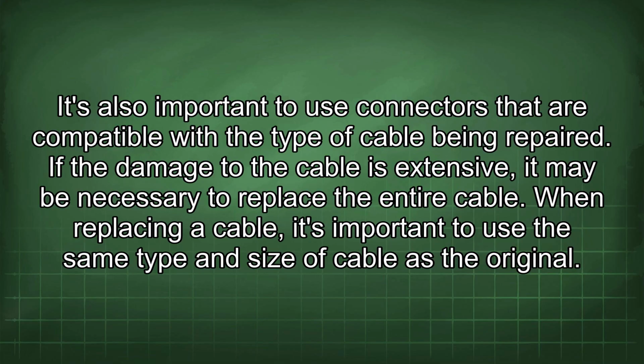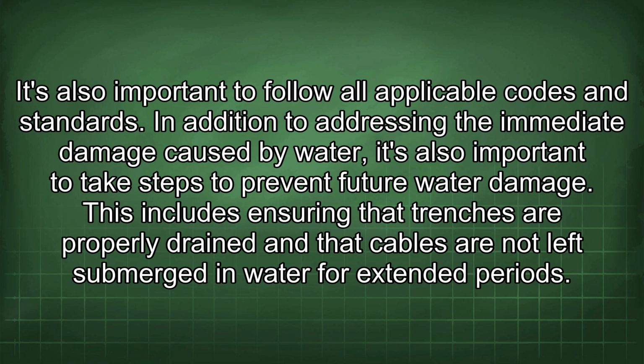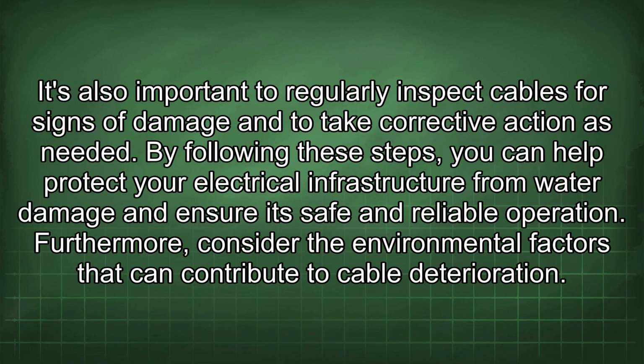If the damage to the cable is extensive, it may be necessary to replace the entire cable. When replacing a cable, it's important to use the same type and size of cable as the original. It's also important to follow all applicable codes and standards. In addition to addressing the immediate damage caused by water, it's also important to take steps to prevent future water damage. This includes ensuring that trenches are properly drained and that cables are not left submerged in water for extended periods. It's also important to regularly inspect cables for signs of damage and to take corrective action as needed.